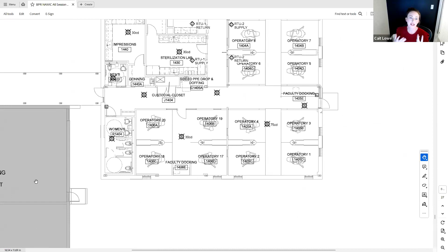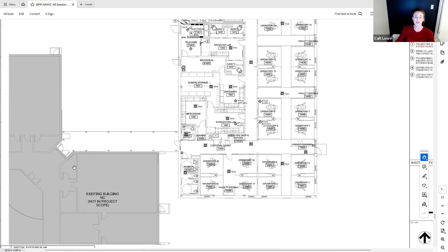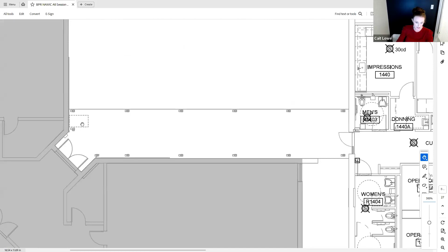It's a little S with the cross, so it's a sensor and it's actually fire alarm. Now all of a sudden I see this hallway, but I didn't see it on another page. I'm like, where's the hallway? It's an existing building, so it's shown as dark. Tammy talked about that in the last session, that means not in contract, but there's something happening between here. My guess is it's the same fire alarm system for the same building tying into the new building, so it's a tie-in point, but I don't know that for sure.